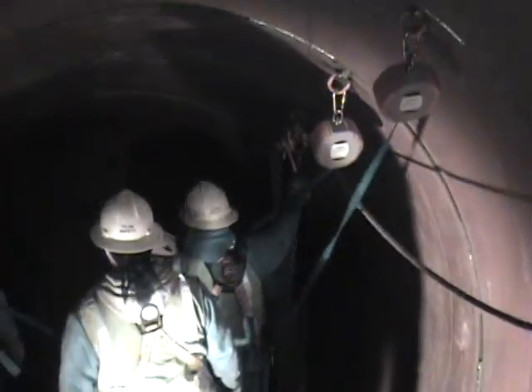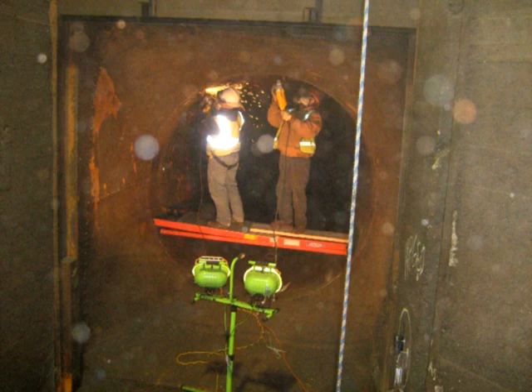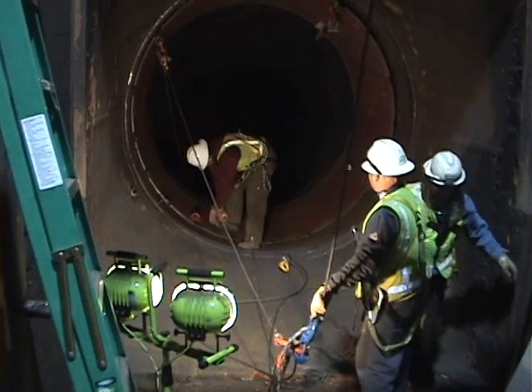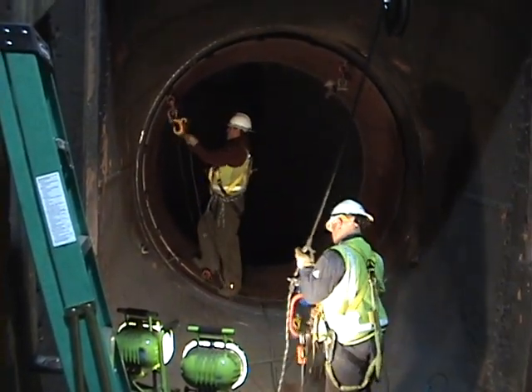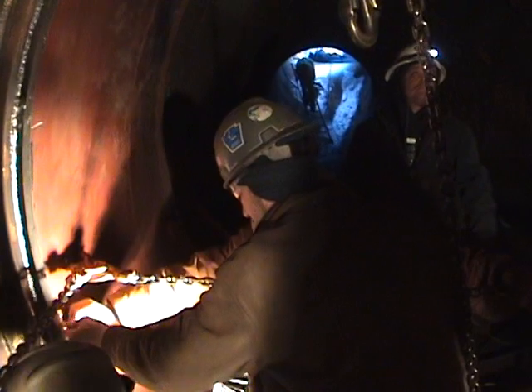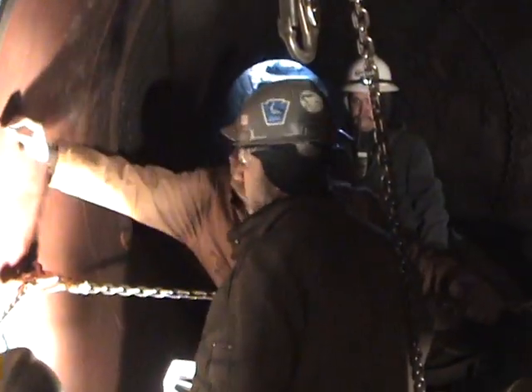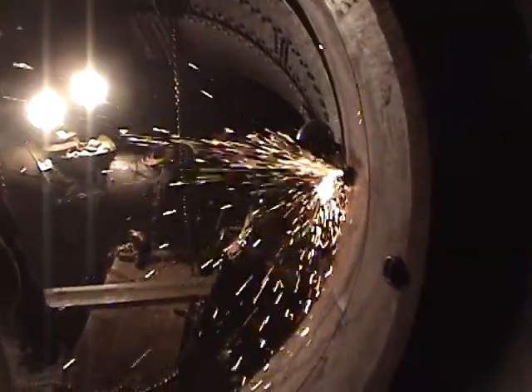When it's snugged into place, we spot-weld four one-foot segments to secure it. We remove the harness and cables and lower them back down the pipe to begin rigging the next section. We grind edges to compensate for occasional small differences in fit, fit up with pry bars, pull it home with come-alongs, then check alignment, check gap, check deflection, and put the grout hole straight up. Then we weld the two sections together.